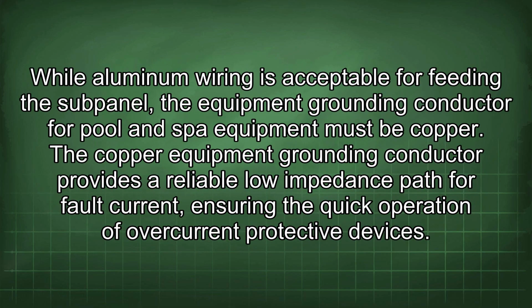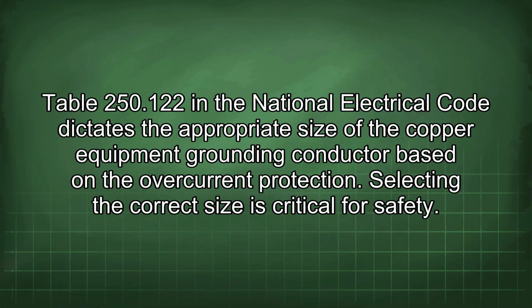While aluminum wiring is acceptable for feeding the subpanel, the equipment grounding conductor for pool and spa equipment must be copper. A copper equipment grounding conductor provides a reliable low-impedance path for fault current, ensuring the quick operation of overcurrent protective devices. Table 250.122 in the National Electrical Code dictates the appropriate size of the copper equipment grounding conductor based on the overcurrent protection. Selecting the correct size is critical for safety.